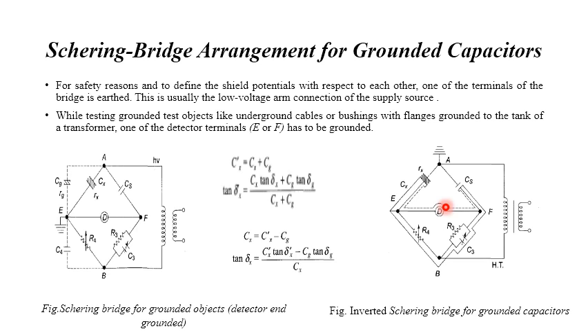So in the case of inverted bridge operation, a self-contained bridge is located inside the Faraday cage at the high voltage terminal, and there is a standard capacitor which is generally mounted on an insulating support. So the variable arms are operated by insulated isolating rods. Sometimes there is an operator himself who will be inside the Faraday cage.